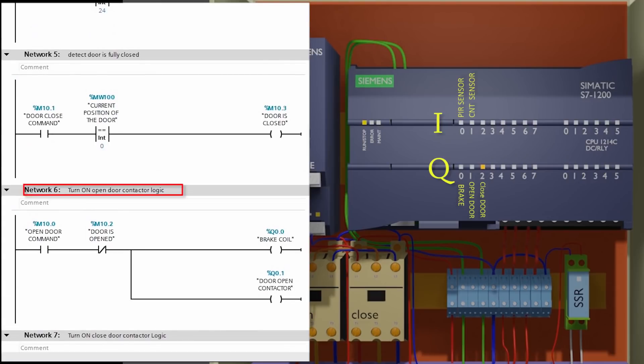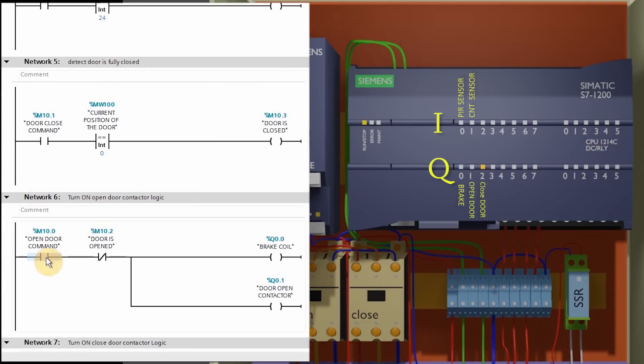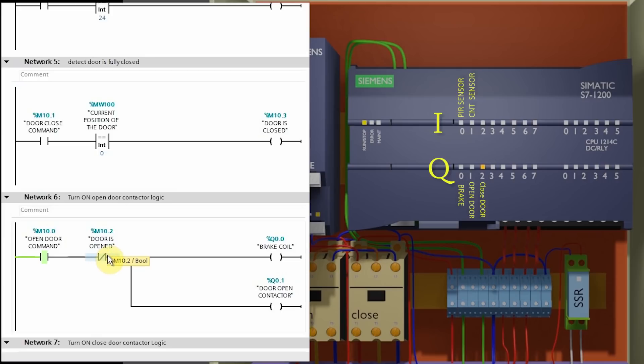Network 6 is to turn on the brake coil and the door open contactor to run the motor. Once M10.0 open door command bit is on, it will turn on the brake coil and the door open contactor. The brake coil and door open contactor will stay off if the door is already in the open position, because we have used the M10.2 normally closed contact in series with the output bits — M10.2 will open if the door is already in the open position.